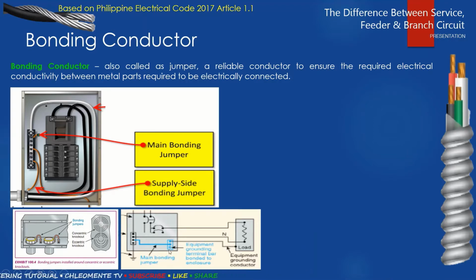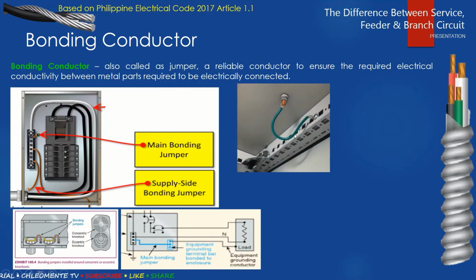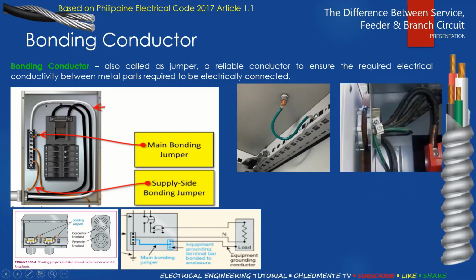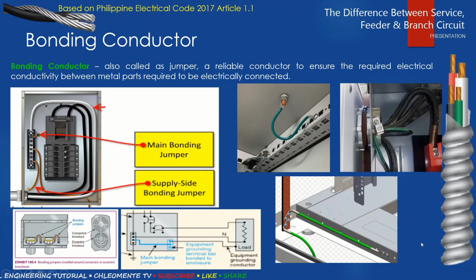So, sa ating main panel, may tinatawag tayong equipment grounding terminal. Dito kinokonekta yung lahat ng equipment grounding conductors galing sa system natin. At meron din tayong main ground bar. Now, dito nakakonekta yung tinatawag na grounding electrode conductors. So, ibinaband yan, no? Pero dapat sa main panel mo lang siya gagawin. Sa sub panel, hindi mo siya i-connect. Wala dapat jumper between yung ground bus at saka isa lang yan. Sa main panel lang yan. And then, papunta sa panel, dito lahat magmumula sa ground bar mo, no? Ito yung mga sample ng ating bonding conductor. Ayan. At saka ito. So, yan ang bonding conductor.